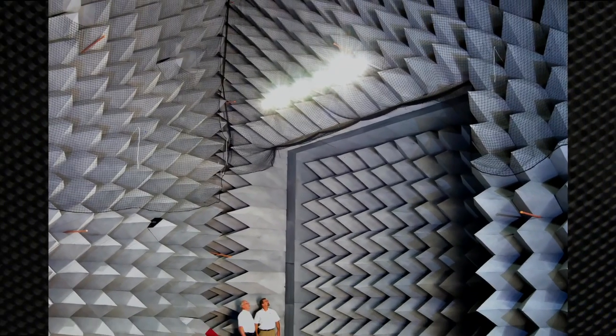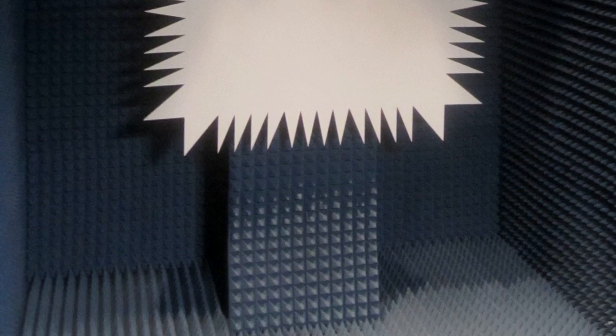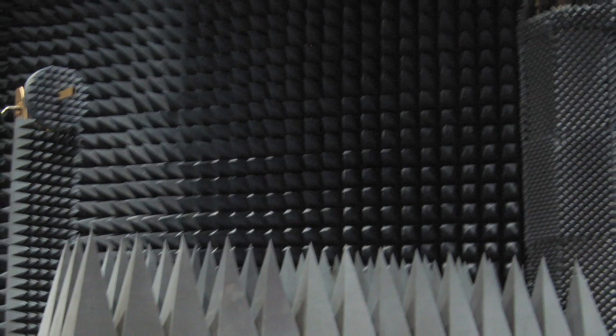As soon as they drain the pressure off the system and the pressure goes down below 15 pounds, our heads will retract back up into the stored position, and they reset the system and they're ready to go back to work. Security is a very high priority dealing with anechoic test chambers. The only person that has to go in there is one of their customers' own people to say, yes, the heads are all back up, go back to work. You can test an average chamber within an hour to 2 hours without anything being removed from the chamber. No absorber has to be removed from the floor, no equipment has to be taken out of the chamber.